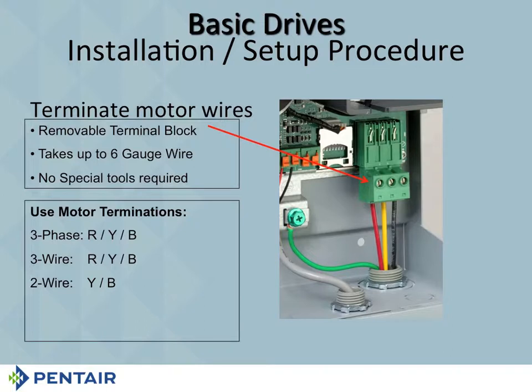All right. And then most importantly, don't forget to connect the ground wire. A drive must be grounded all the way back to the main breaker. That's where you want to ground it. You don't want to ground it anyplace else. You want to ground it all the way back to the main breaker. So bring it in here and connect it to that grounding lug there.